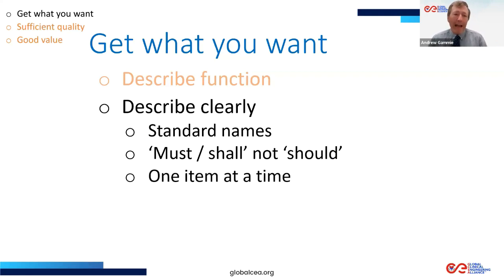It's useful too to have a habit of asking for one item at a time. You see, if you ask for maybe a new ICU, you say, I want a pulse oximeter and an ECG recorder, you might get two different devices, you might get a multi-parameter patient monitor, or you might just get one with a little bit of something, part of an ECG, on the side. Just do it one at a time. Ask for your multi-parameter monitor with all the parameters listed, or get your pulse oximeter in one specification and your ECG in another, if that's what you want. But make sure you've got one specification for one device or application.